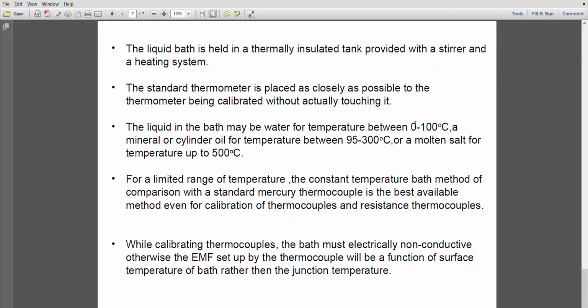Liquid in the bath may be water at 0 to 100 degrees, a mineral or cylinder oil for temperature between 95 to 300, or a molten substance. These are different heating substances used depending on the temperature range for calibration.